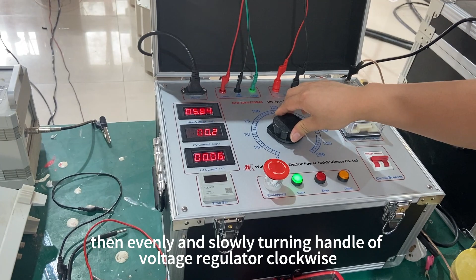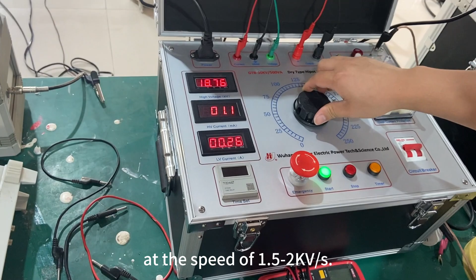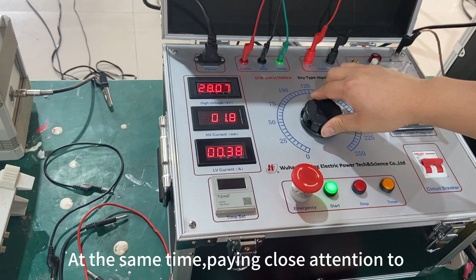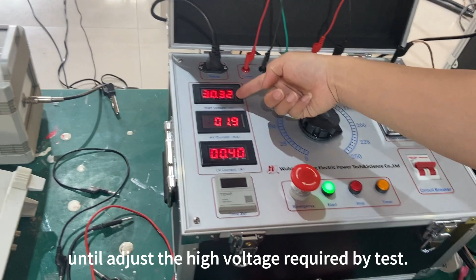Then evenly and slowly turn the handle of the voltage regulator clockwise, at the speed of 1.5-2kV per second. Make the high voltage gradually rise, while paying close attention to the indication and testing products of the ammeter, until you adjust to the high voltage required by the test.